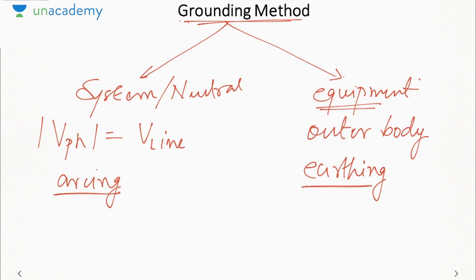Grounding refers to grounding the neutral of a system to avoid any system damage due to high voltage, and earthing refers to grounding the outer body of the equipment to release the stored charges into the ground, or to provide a low resistance path for the flow of charge into the ground that will protect the operator of the equipment from any shock. So these two types of grounding methods are generally used. Our focus will be on the system or the neutral grounding. So let us see what are the various types in which we can ground the neutral of a system.